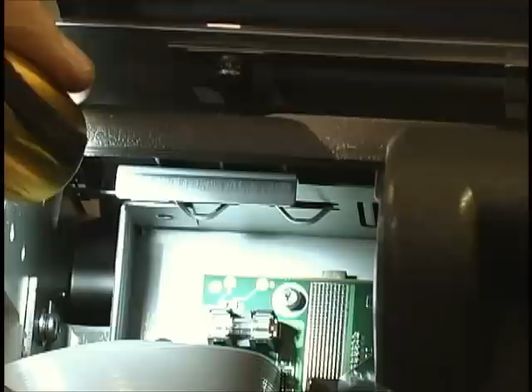Next thing we're going to do is a resistance check to make sure that the trailing cable is on correctly. If it's not on correctly, you can blow a fuse on the motherboard, F7. In this case, F7 is right there where we're looking. So what you want to read on your ohm meter is between 100 and 200 ohms, or maybe even a little higher. These are the two test points, these two right here. Since I'm holding a flashlight, it's kind of hard for me to actually put the test points on to show it to you. But I'm going to measure this without the flashlight before I power up to make sure I have something other than 0 or infinity.